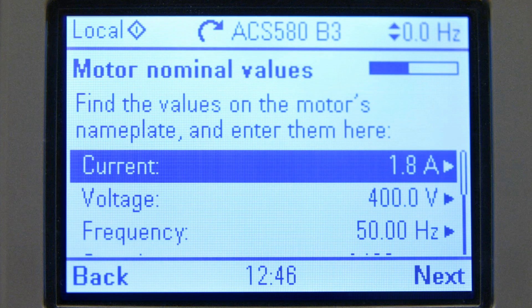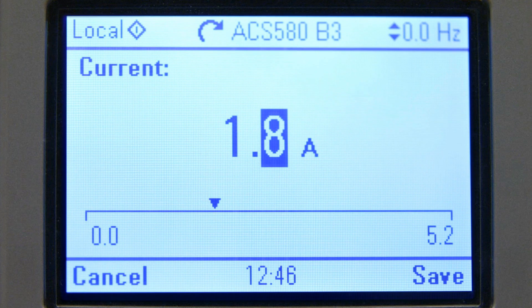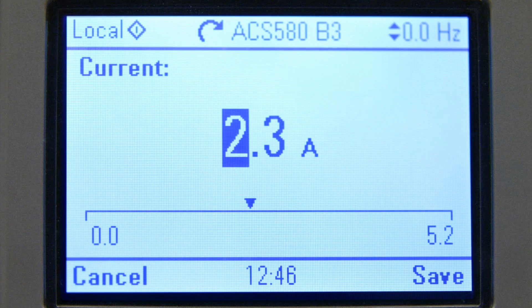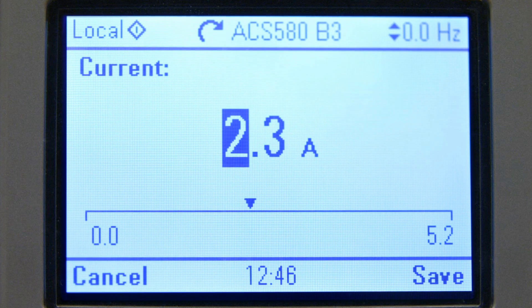The most critical values needed for the commissioning are the motor nominal values. Make sure that the values are the same as on the motor nameplate.